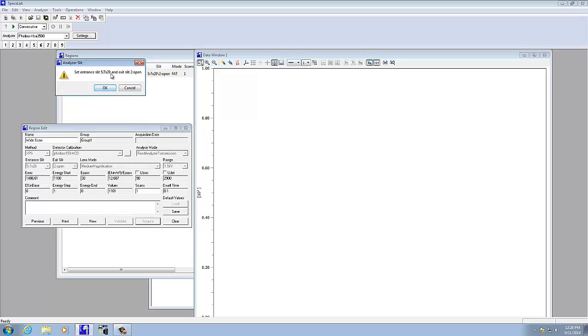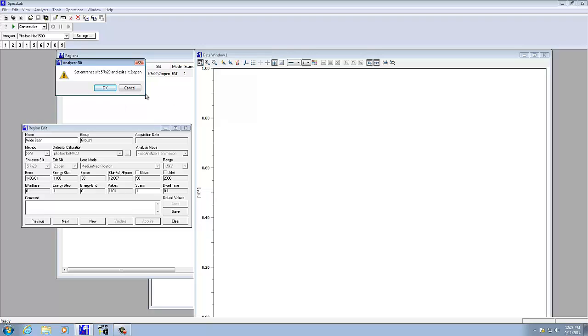This is just a reminder. It reminds us that the entrance slit and exit slit should be that. If you ever need to change the entrance or exit slit, the software itself doesn't change that. It just tells the analyzer what they're set at. Please contact either Dr. Wagner, Dr. Dunham, or Dr. Michalestrom if you need the actual entrance and exit slit to change because that's a mechanical switch that has to be changed.